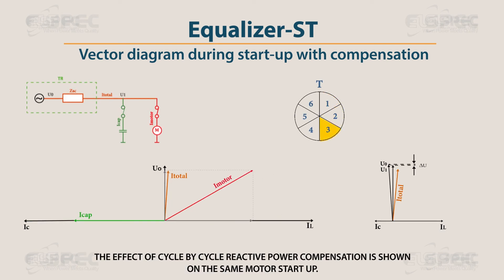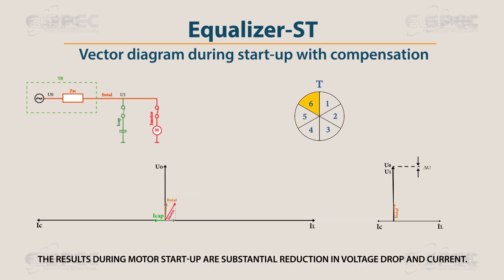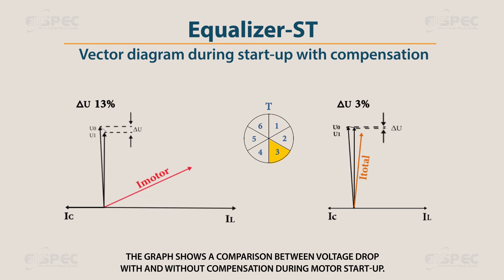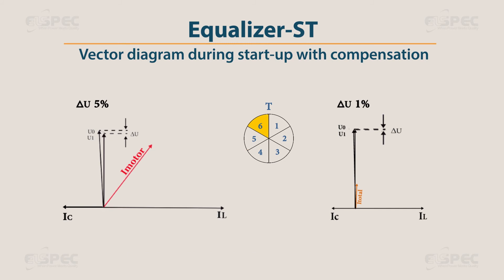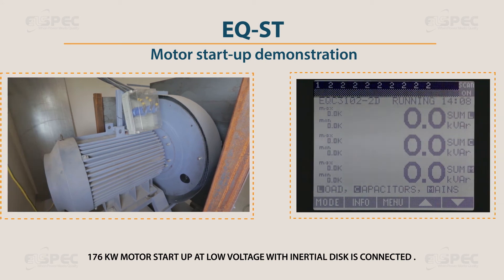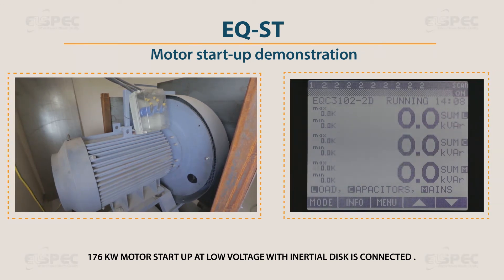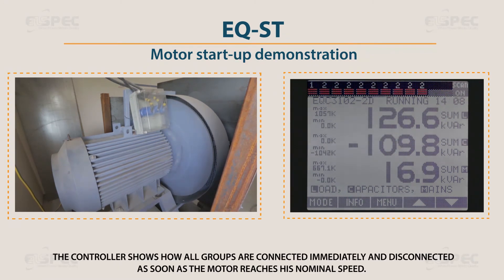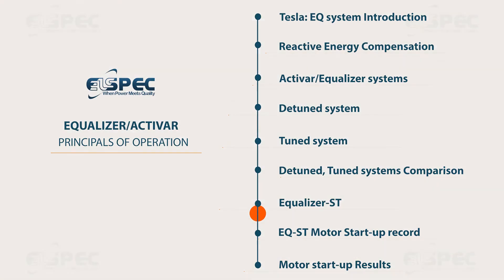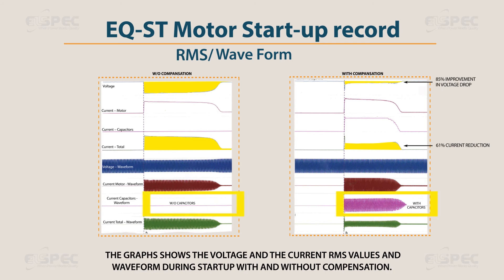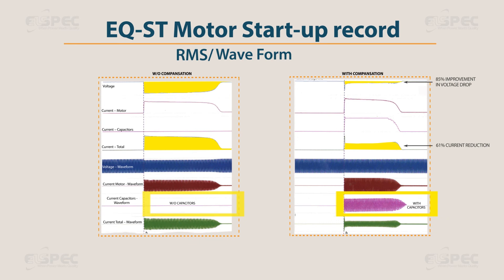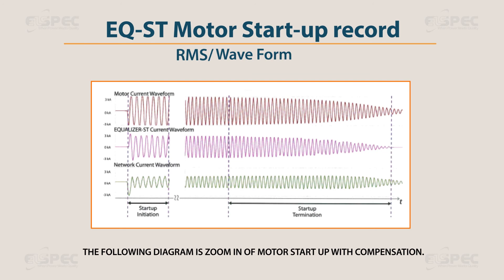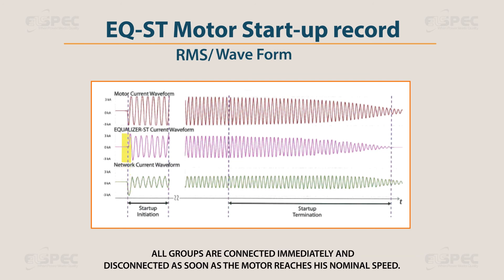The effect of cycle-by-cycle reactive power compensation is shown on the same motor startup. The results during motor startup show substantial reduction in voltage drop and current. The graph shows a comparison between voltage drop with and without compensation during motor startup, resulting in substantial improvement. The next demonstration is a 176-kilowatt motor startup at low voltage with an inertial disk connected. The controller shows how all groups are connected immediately and disconnected as soon as the motor reaches its nominal speed.